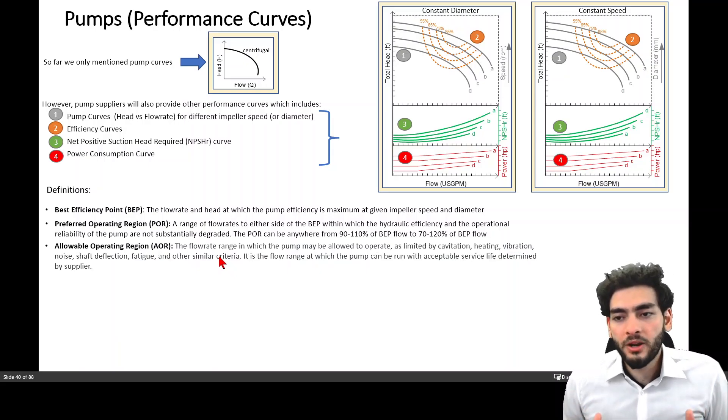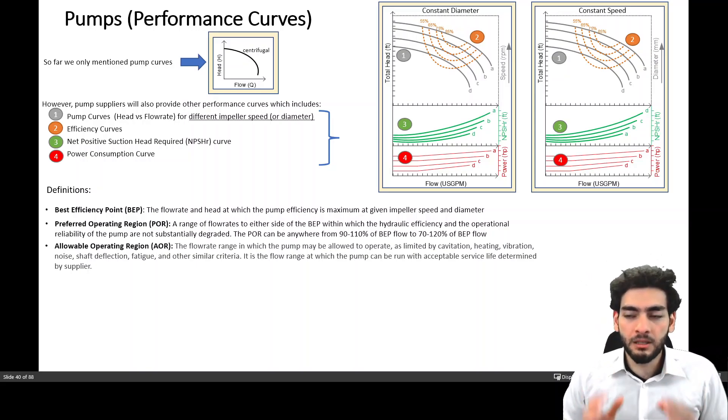The allowable operating region is the flow rate range in which the pump may be allowed to operate as limited by cavitation, heating, vibration, or noise, and other similar criteria. It's a flow range at which the pump can be run within acceptable service life determined by the supplier.